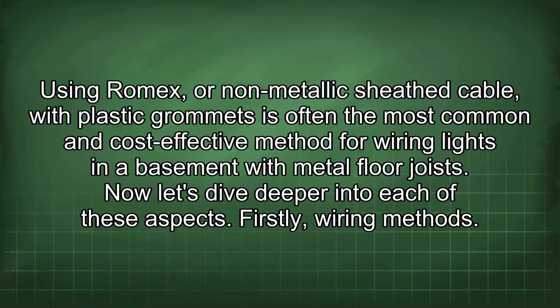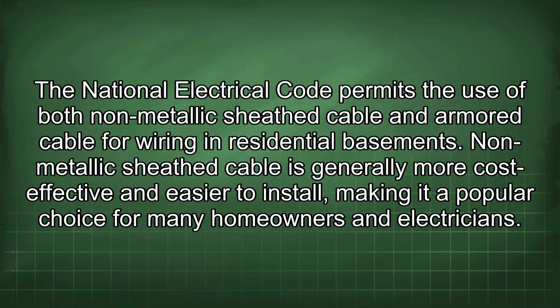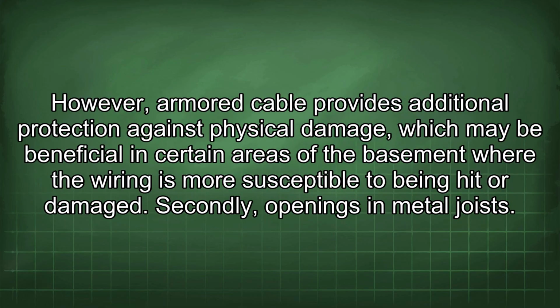Firstly, wiring methods. The National Electrical Code permits the use of both non-metallic sheathed cable and armored cable for wiring in residential basements. Non-metallic sheathed cable is generally more cost-effective and easier to install, making it a popular choice for many homeowners and electricians. However, armored cable provides additional protection against physical damage, which may be beneficial in certain areas of the basement where the wiring is more susceptible to being hit or damaged.